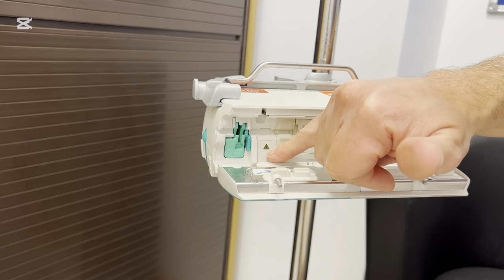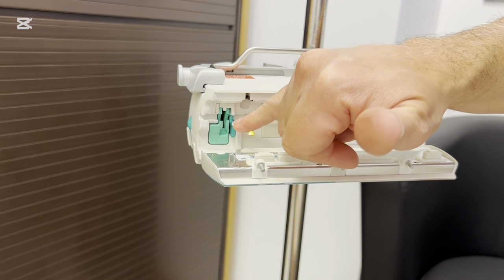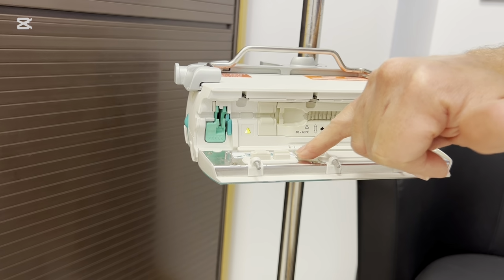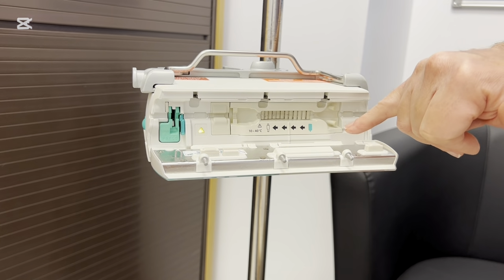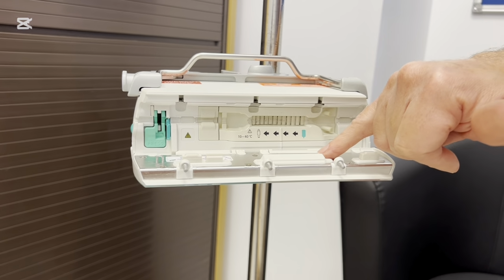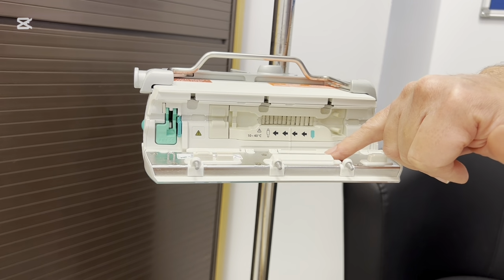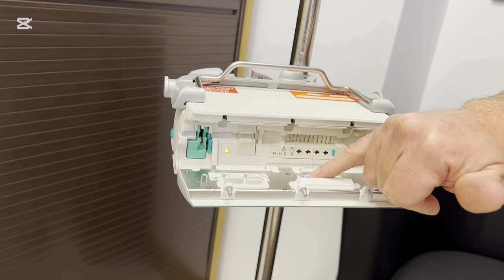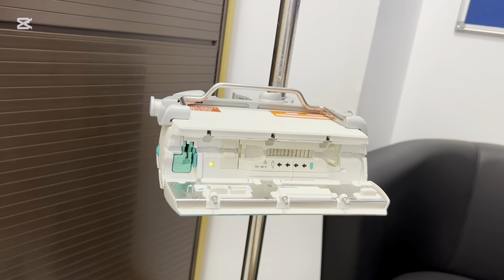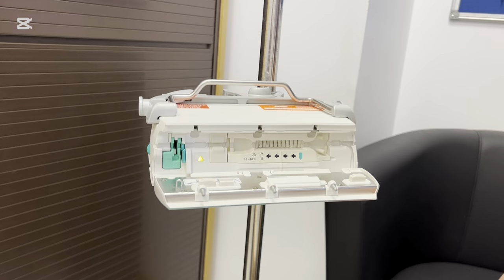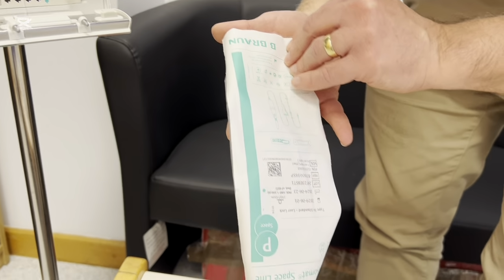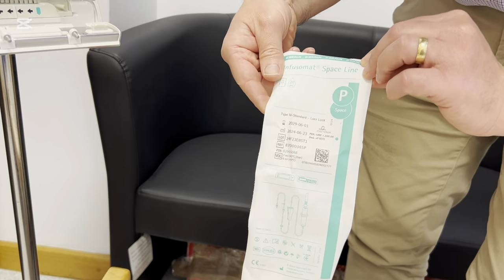This tells you that needs to be flashing. If it's not flashing, and you insert the clip, it will potentially sever the line. And likewise here, you've got two different shaped poles, and the important thing is to make sure you don't twist the administration set, otherwise it won't pump properly through the pumping segment. So take your administration set for this device, which is a B-Braun space line.